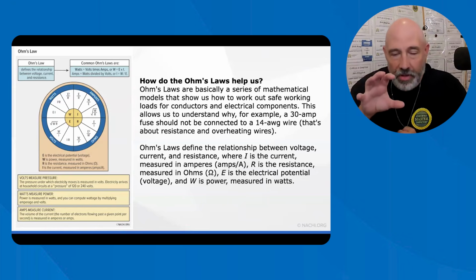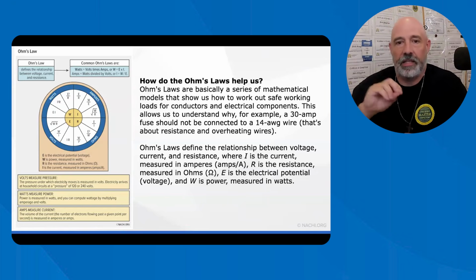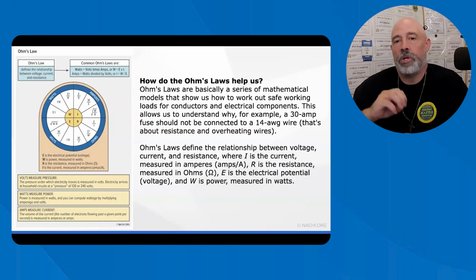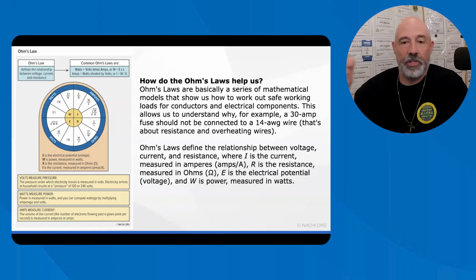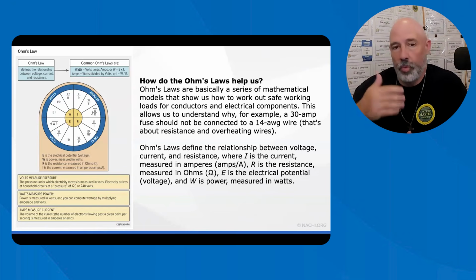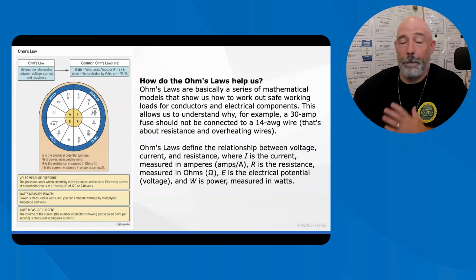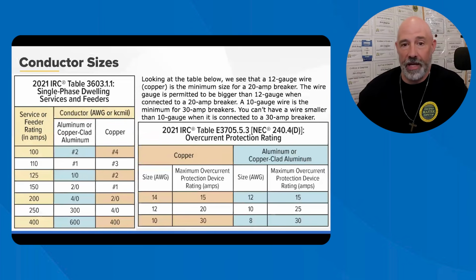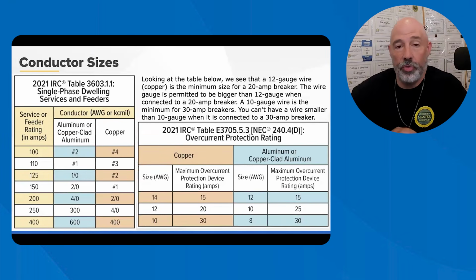Now, as home inspectors, you might not get all this, and that's okay. What you should get is, if you see a 14 gauge wire on a 20 amp circuit, you should be calling that out. If you see it on a 30 amp circuit, you should be calling that out. Try to understand what relates to what amps. Those are a big thing to look at. The only exception, I believe, is air conditioners, and check the jurisdictions when you do those types of home inspections.